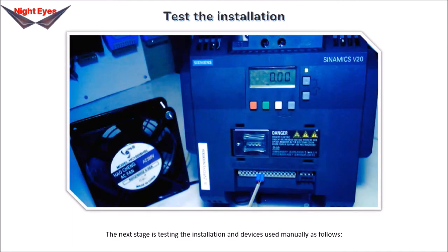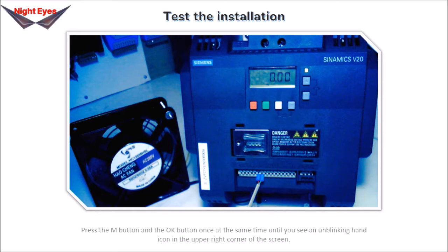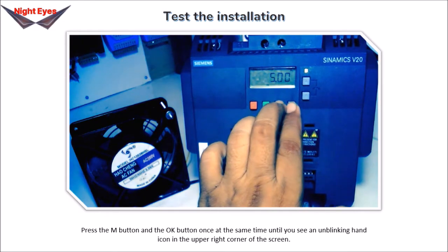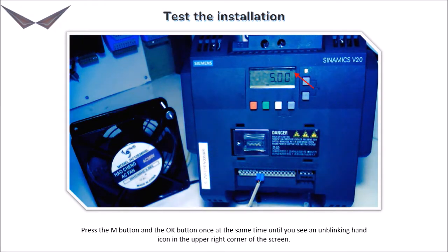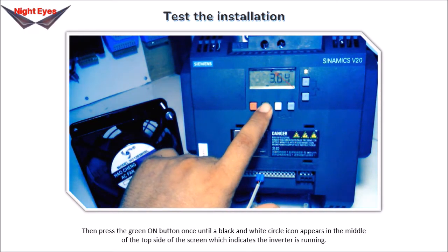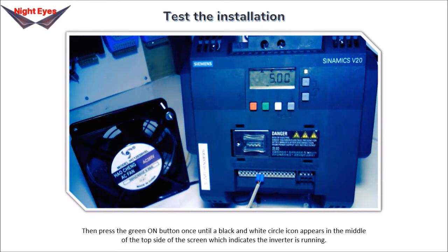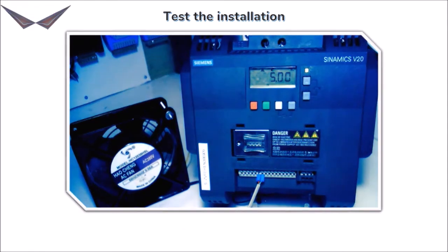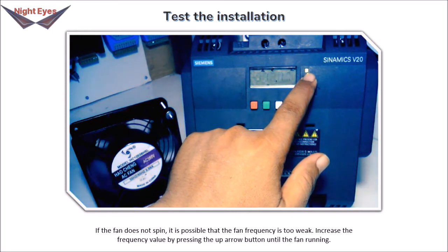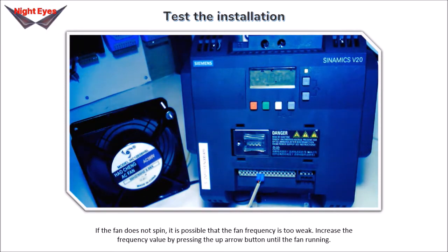The next stage is testing the installation and devices manually. Press the M button and the OK button simultaneously until you see an unblinking hand icon in the upper right corner of the screen. Then press the green ON button until a black-and-white circle icon appears at the top of the screen, indicating the inverter is running. If the fan does not spin, the frequency may be too weak — increase the frequency by pressing the up arrow button until the fan runs.